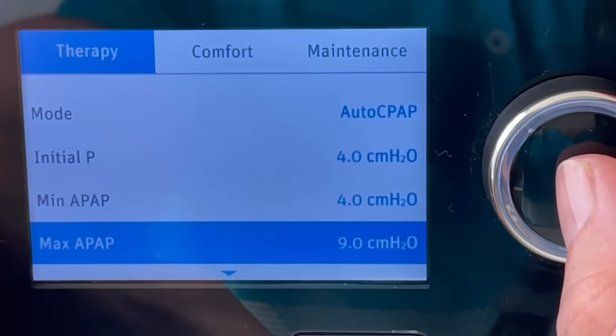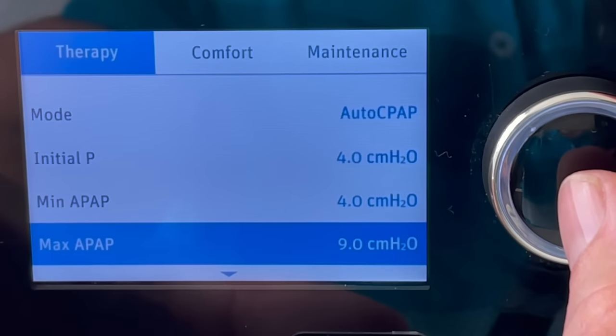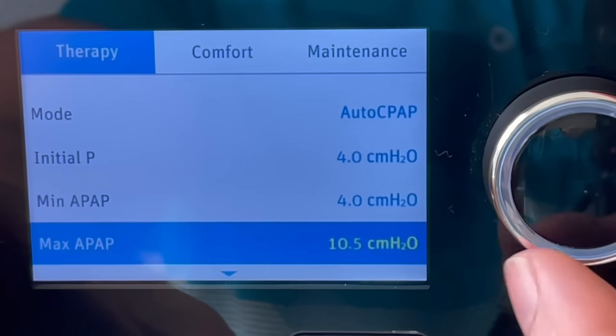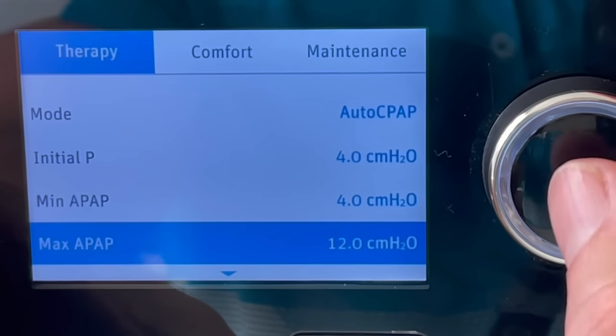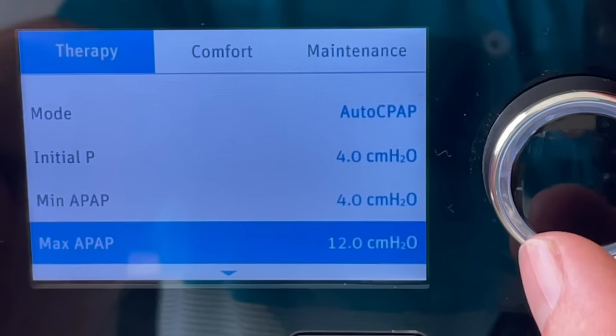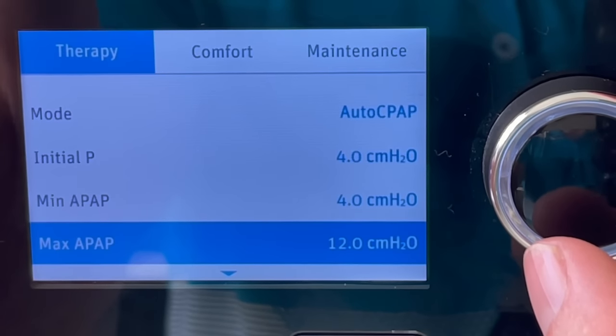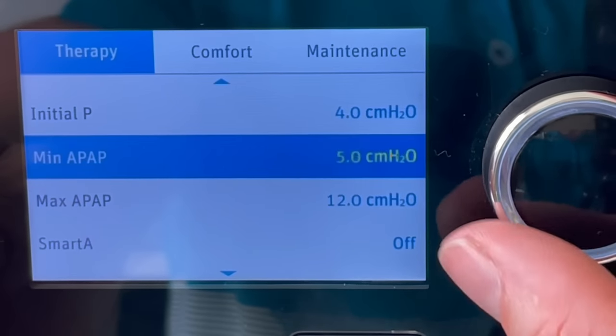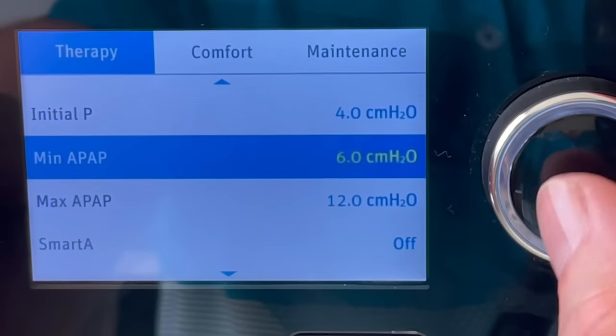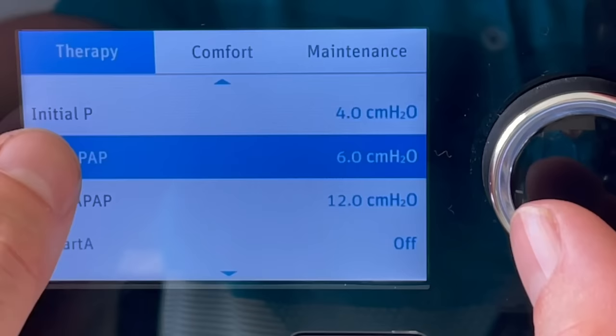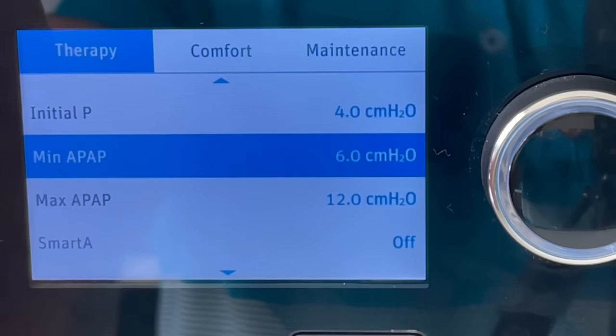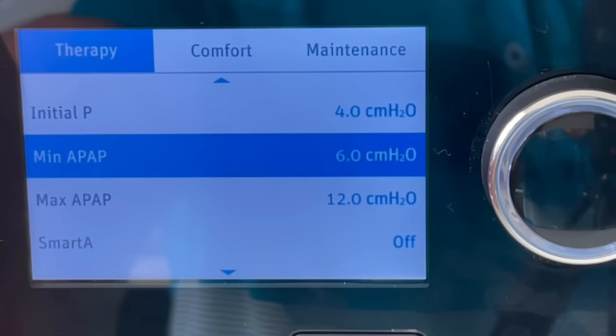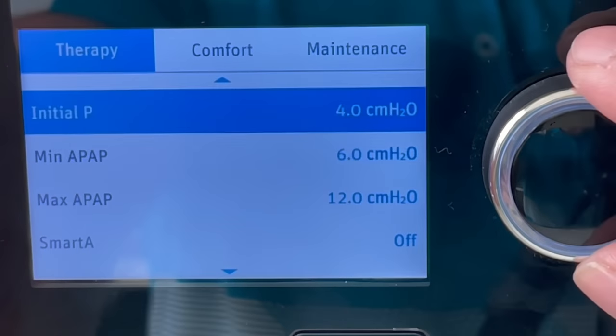Even without access to any pressure data, you can basically just do some trial and error based on your apnea-hypopnea index. Let's say I had it at nine and checked the next morning and it came in at 15 — that's pretty high. I'd need to have this a little bit higher, I might try 12 the next night. Then I look at it the next day and the apnea-hypopnea index has dropped from 15 down to seven — I know I'm near where I need to be. I might bring the min up a little bit just to give it more support at the lower end. But you can basically just have a play around with these two values to find what is comfortable for you, and use your apnea-hypopnea index to guide you as to whether the therapy is effectively controlling your sleep apnea. Pretty straightforward.